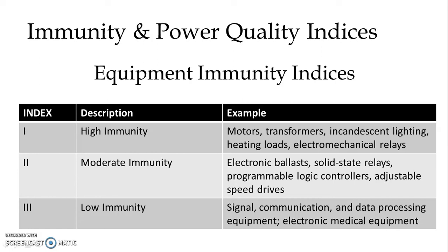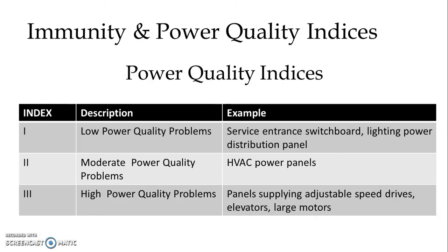Now, immunity and power quality indices. We have equipment immunity indices with index one, two, and three, corresponding to high immunity, moderate immunity, or low immunity. Examples of high immunity include motors, transformers, incandescent lighting, heating loads, and electromechanical relays. For moderate immunity we have electronic ballasts, solid state relays, programmable logic controllers, and adjustable speed drives. For low immunity we have signal, communication and data processing equipment, as well as electronic medical equipment.